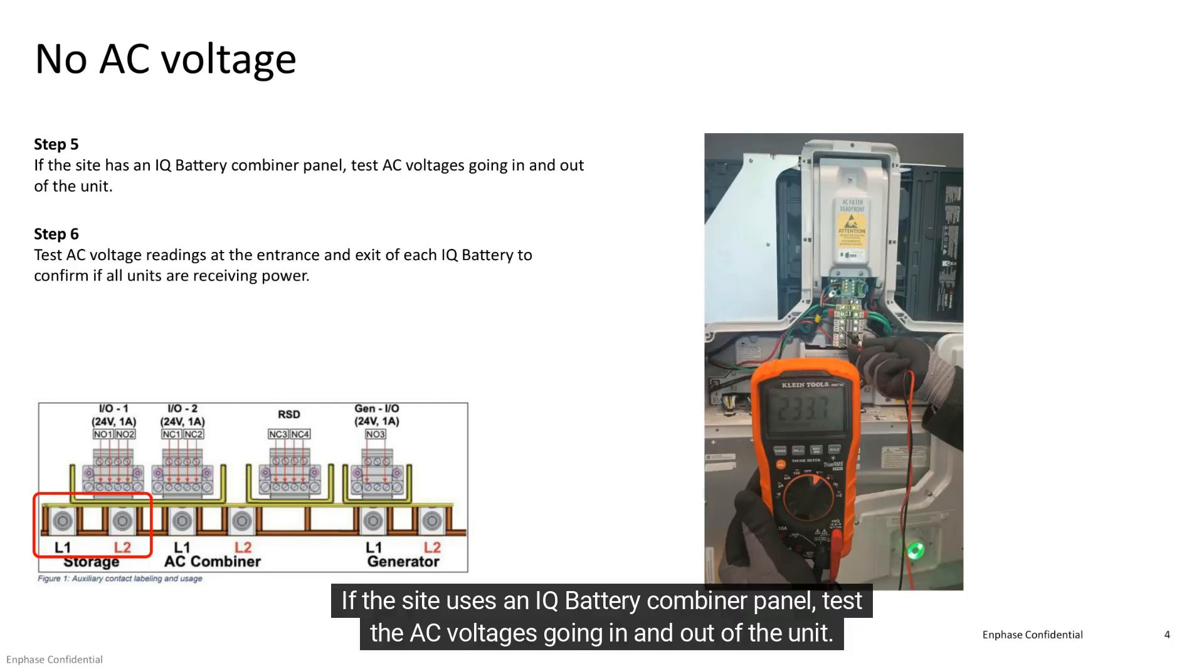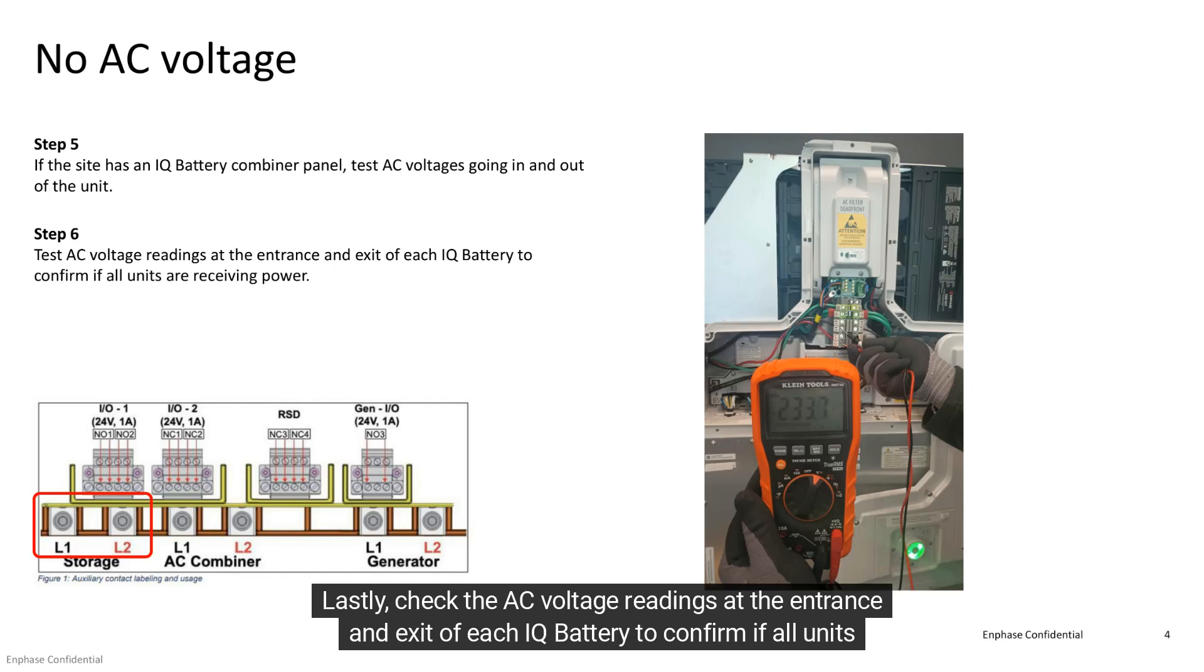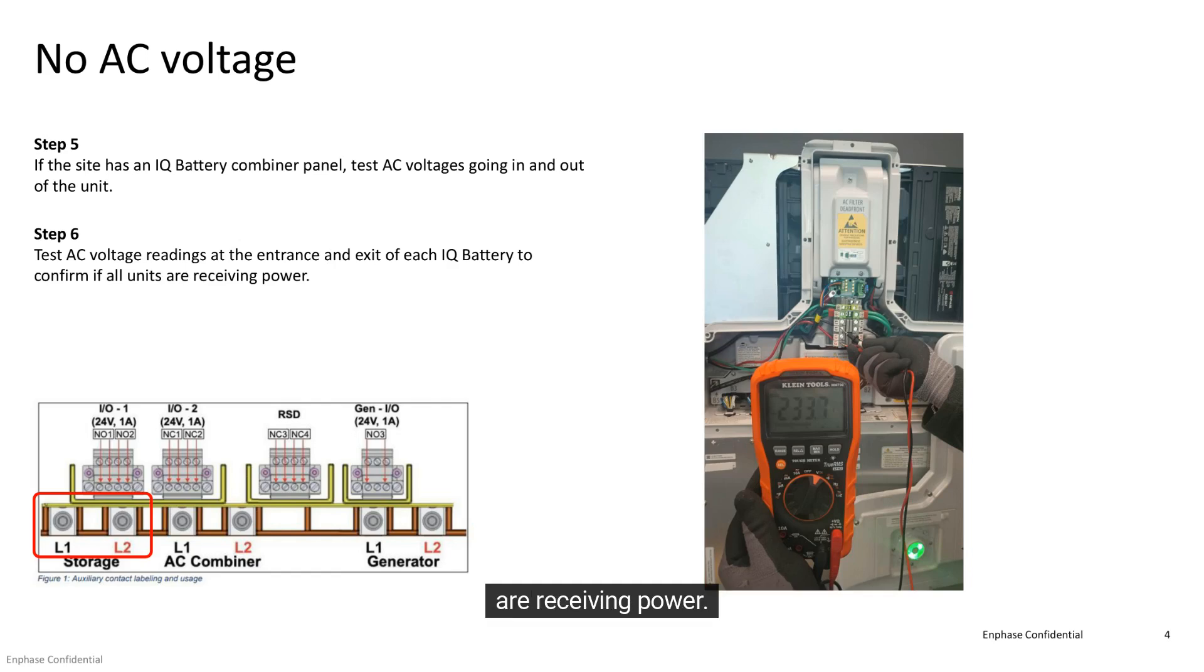If the site uses an IQ Battery combiner panel, test the AC voltages going in and out of the unit. Lastly, check the AC voltage readings at the entrance and exit of each IQ Battery to confirm if all units are receiving power.